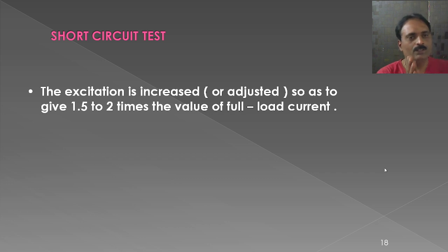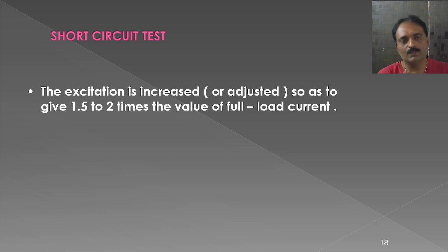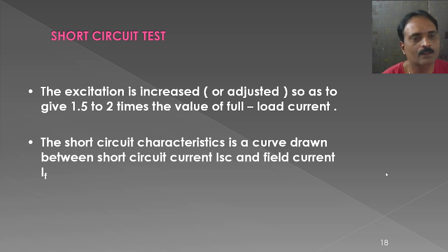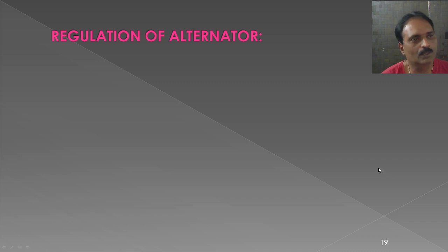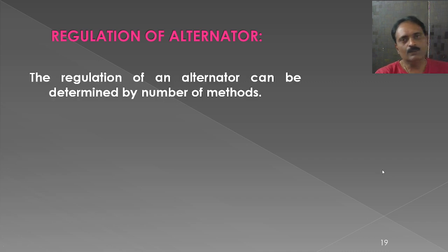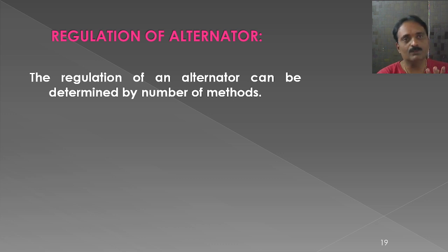The short circuit test is generally conducted up to 150% to 200% of the full load current value. There are many methods to calculate the regulation of an alternator — synchronous impedance method, ZPF (zero power factor) method, MMF method, and others — but here we discuss the synchronous impedance method, for which the open circuit test and short circuit test data are essential.